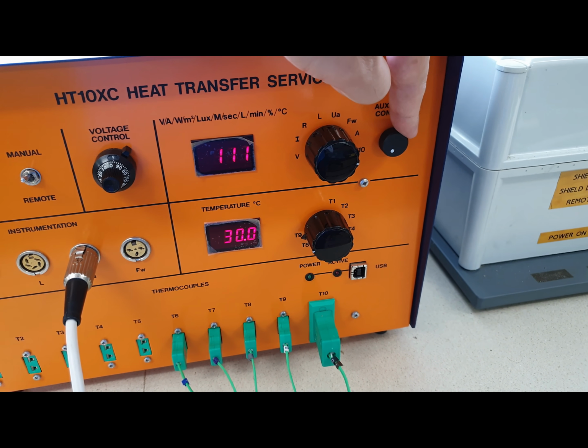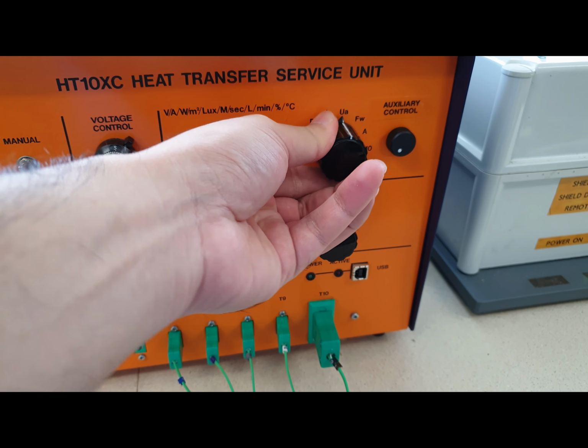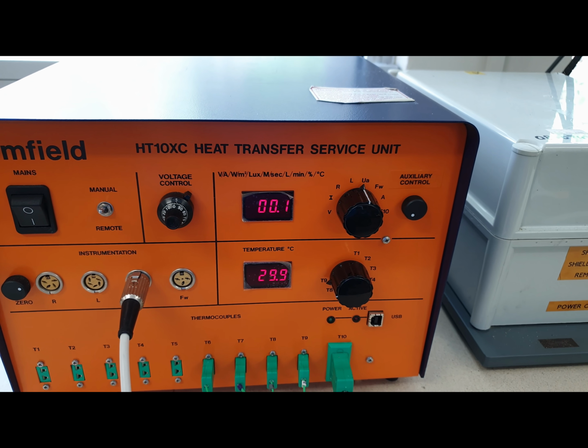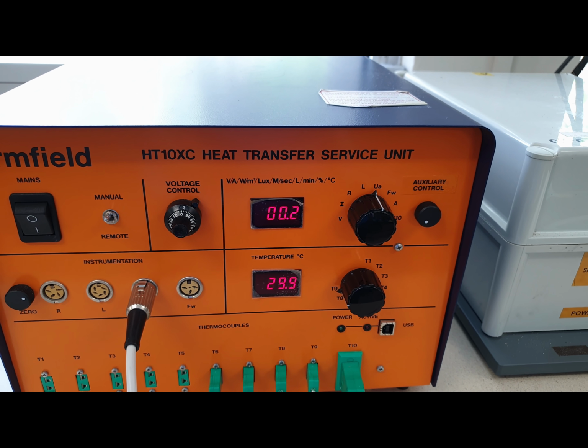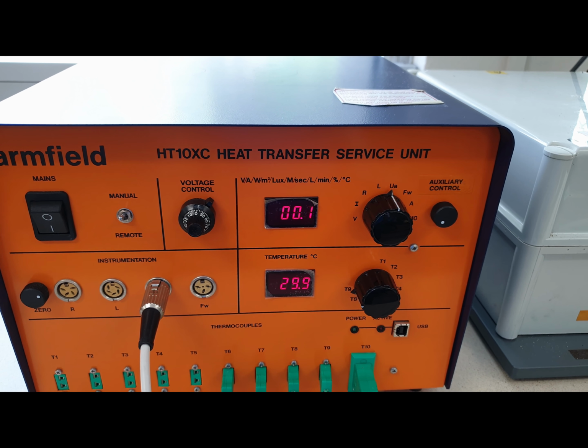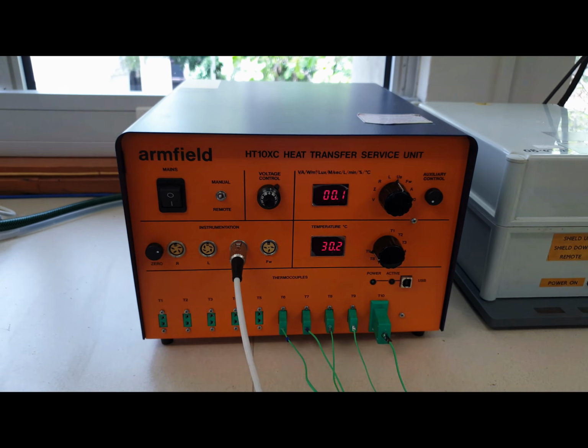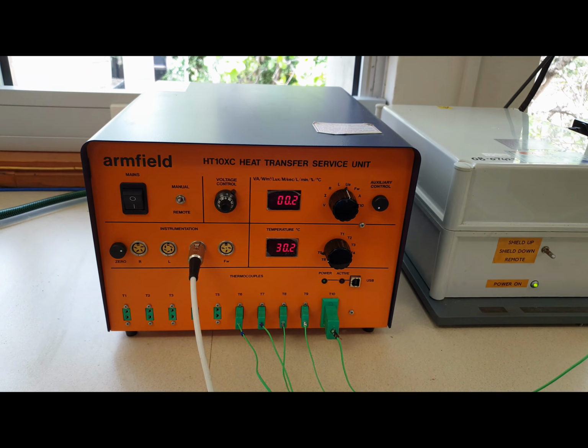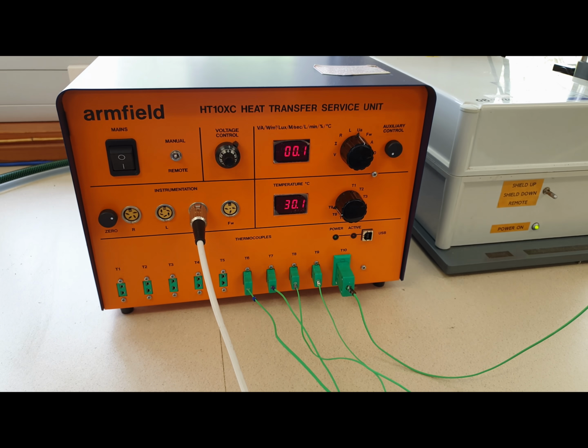I can check the velocity with this selector, and as you can see, it's 0.1, 0.2, and it is because of natural convection happening there. So we don't have any forced convection there.